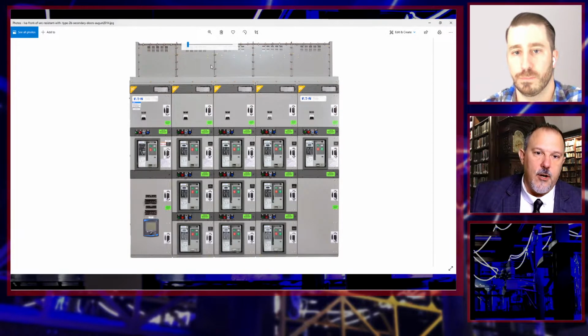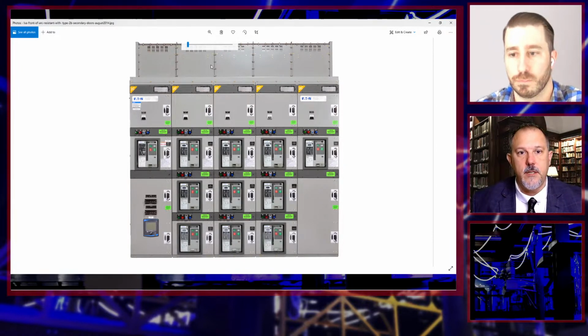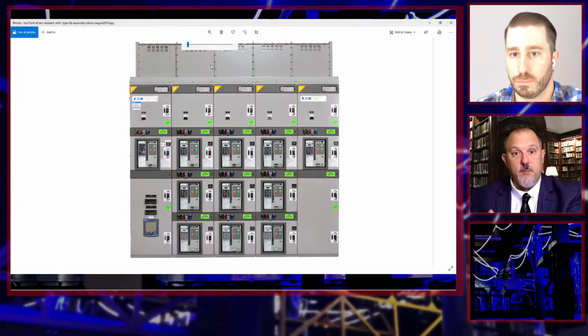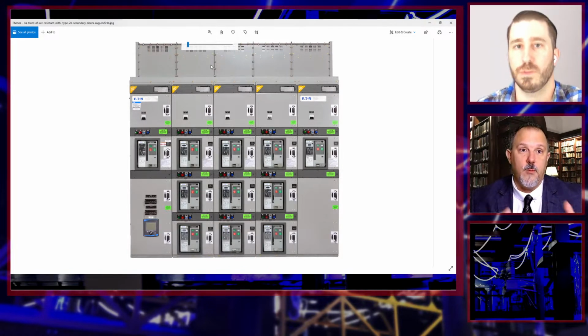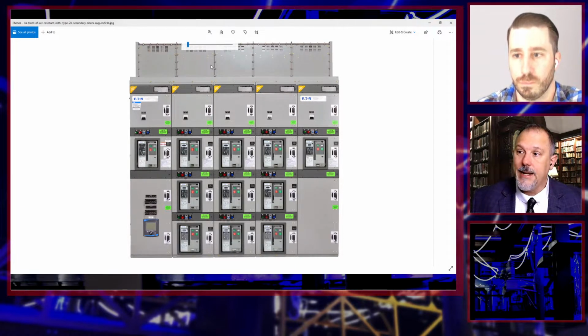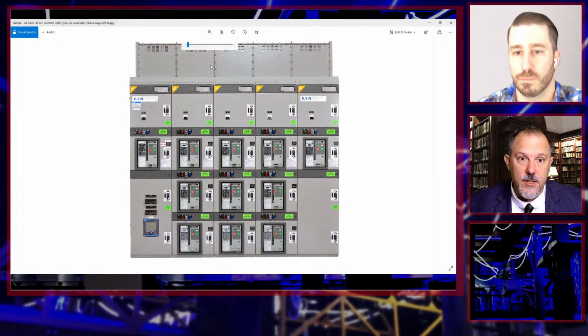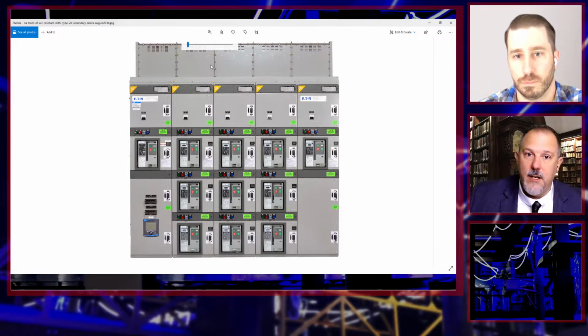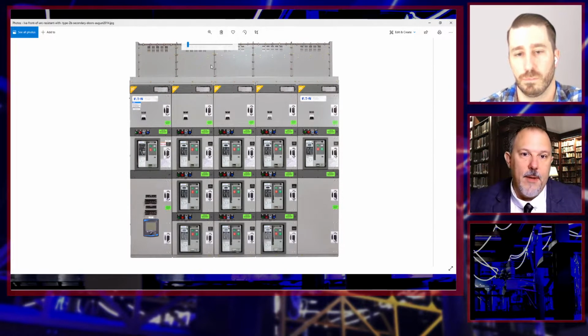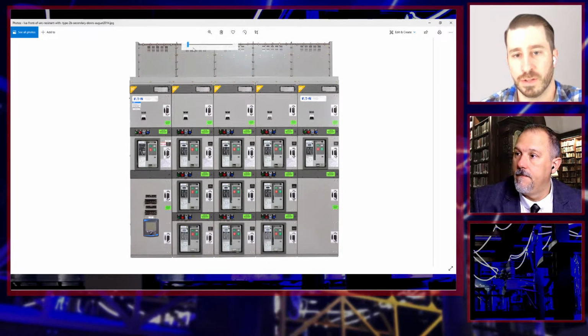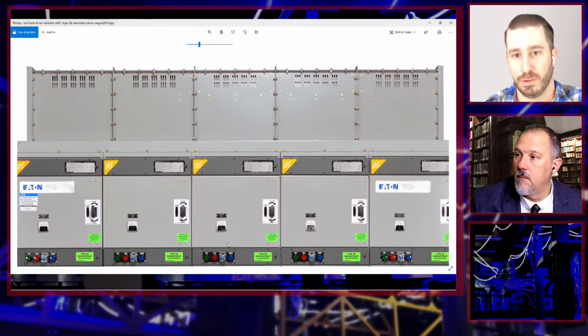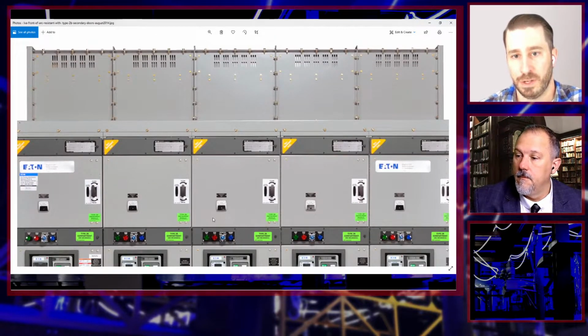You can try to reduce the arcing currents that are in there to protect the equipment, because now we have a lower current. We've got that three-phase bolted fault current that we have to brace it for. But then we have to say, what happens when an arc occurs inside? How do I respond? I can either try to reduce it and clear it fast, or the other concept is I'm going to contain it and put these big baffles up on the top and just funnel that energy up and out. There's a lot of effort in the design of this equipment to try to handle that fault current as well as mitigate the effects.